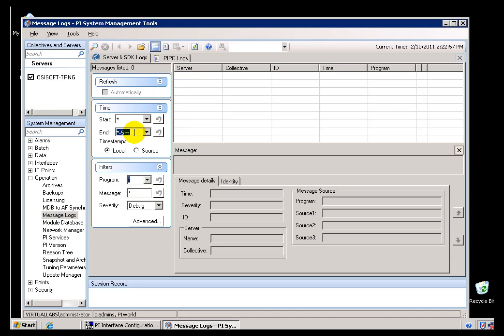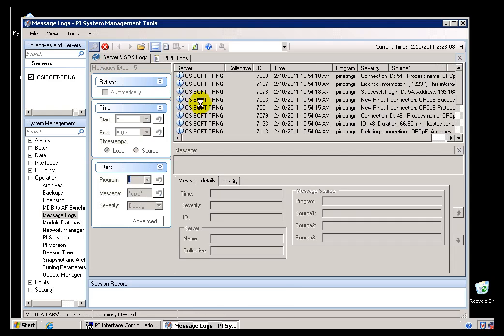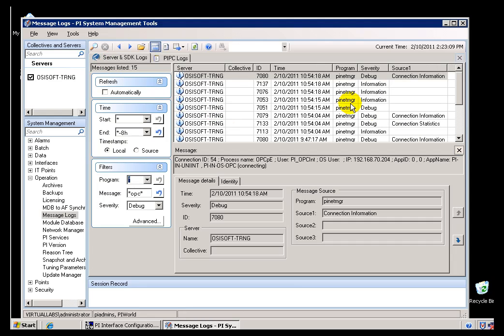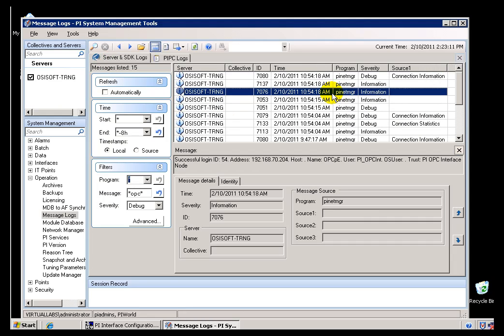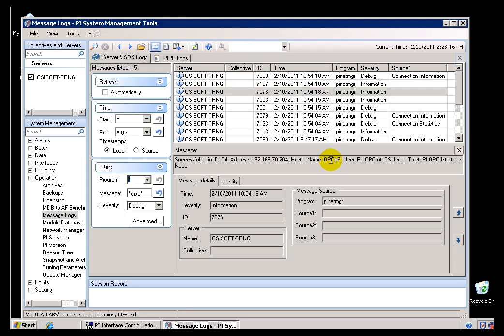Let's go with eight hours, anything that had the word OPC in it. So what I'm doing is I'm searching for any Messages from when the OPC Interface tried to connect. And yes, as you can see right here, these are the Connection Credentials that are being passed by the OPC Interface by default.